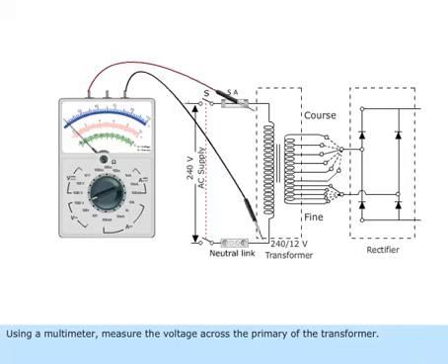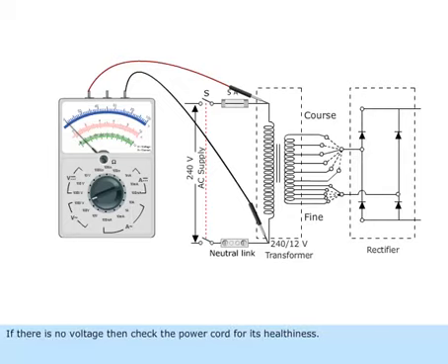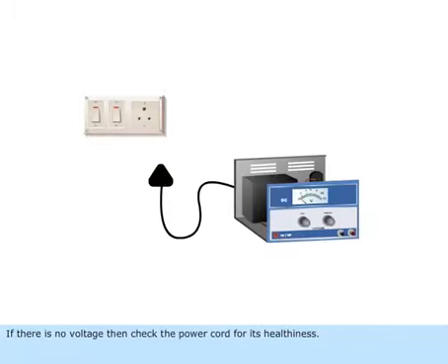Using a multimeter, measure the voltage across the primary of the transformer. If there is no voltage, then check the power cord for its healthiness.